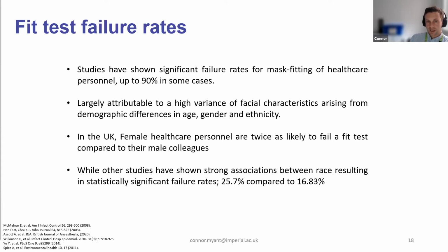In the UK, we found that female healthcare personnel are twice as likely to fail a fit test compared to their male colleagues. And some other studies have shown that there's a strong association with race, resulting in significant failure rates for non-white demographic groups. So we found groups as high as 25% failure rates compared to white being around about 16% failure rate.